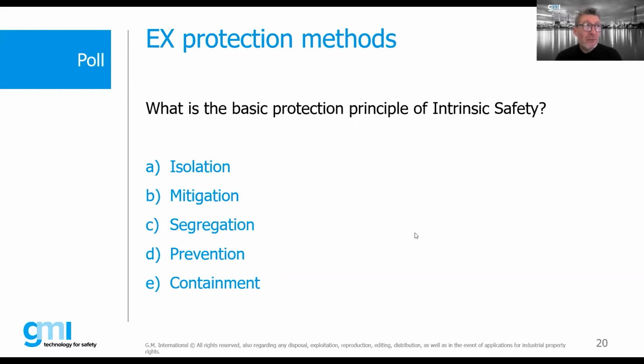As we go along, maybe you can also mention whether dust also applies to this. That is a question that has come up with regards to dust hazards. Certainly, intrinsic safety is a suitable protection concept for dust. The whole idea with dust hazards is making sure that any dust that collects on electrical components or equipment doesn't ignite, so we need to be concerned about the external temperature of the equipment. We also want to make sure no ignitable amounts of dust can get inside our enclosures, so we have minimum IP ratings required for dust hazards, as well as maximum surface temperature ratings associated with equipment suitable for dust applications. Intrinsic safety certainly falls within that.